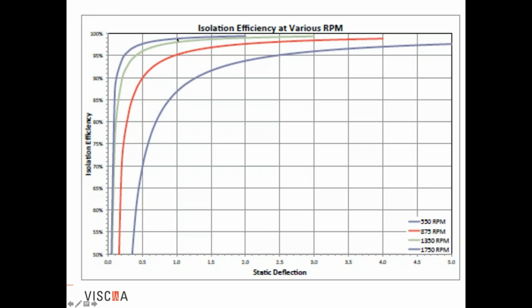Nominal being if the spring has a stiffness of 1,000 pounds per inch and I'm rating it at 1,000 pounds to have a 1-inch deflection. Actual is what's going to happen when the piece of equipment goes on top of it. I can't force 1,000 pounds onto my spring, and you never want to overload your spring. So in general, in actual installation, I may only have 800 pounds on that spring. So my actual deflection is 0.8, where my nominal is 1. But if you look at this chart here, moving from a 1-inch to a 0.8-inch deflection, there is no sensitivity or hardly any sensitivity on the isolation efficiency.